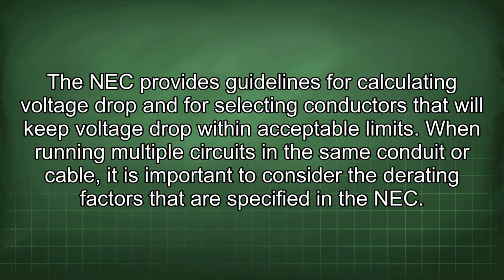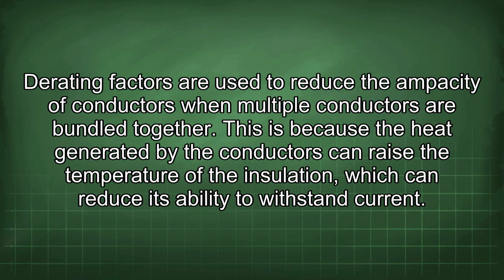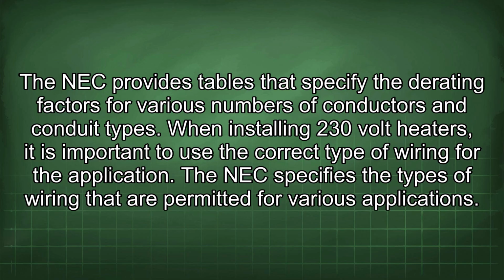When running multiple circuits in the same conduit or cable, it is important to consider the derating factors that are specified in the NEC. Derating factors are used to reduce the ampacity of conductors when multiple conductors are bundled together. This is because the heat generated by the conductors can raise the temperature of the insulation, which can reduce its ability to withstand current. The NEC provides tables that specify the derating factors for various numbers of conductors and conduit types.